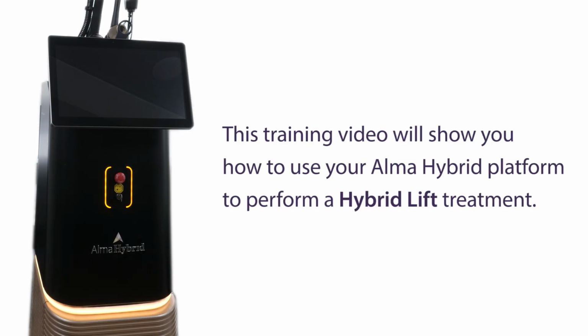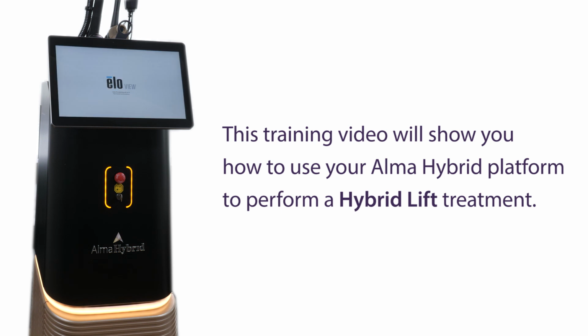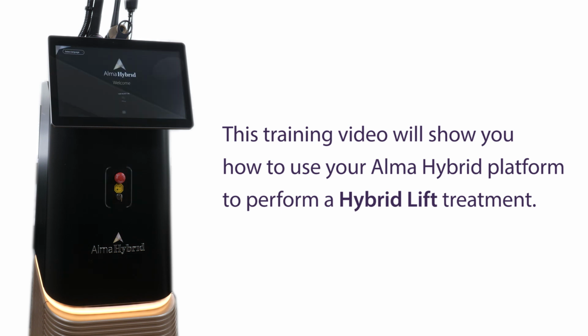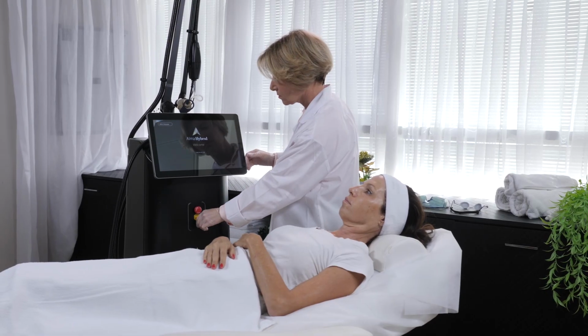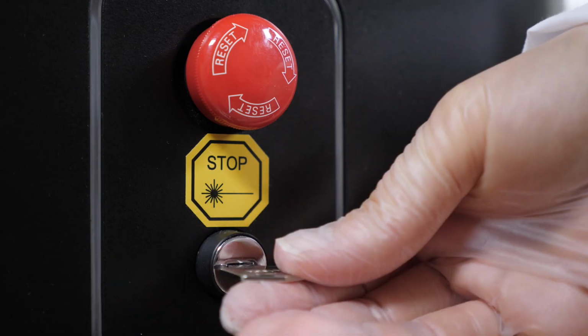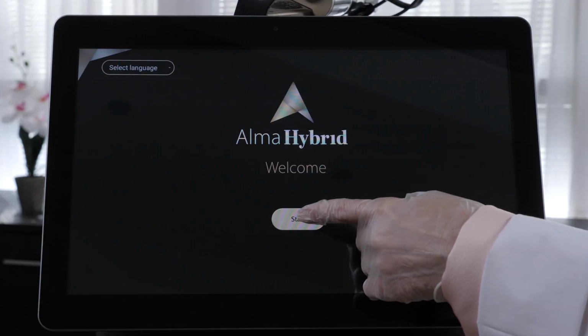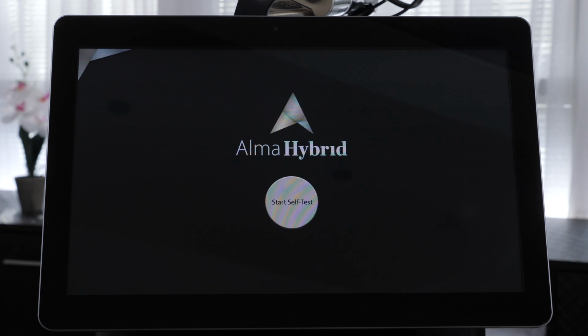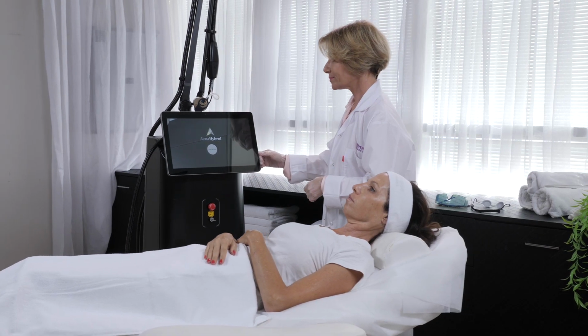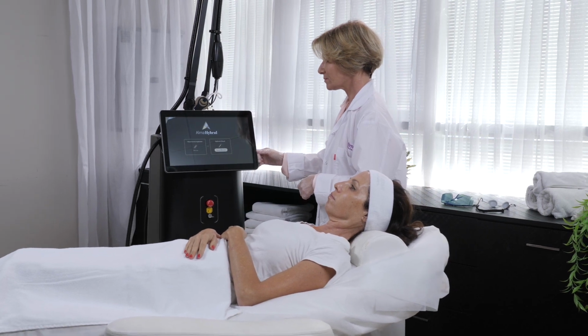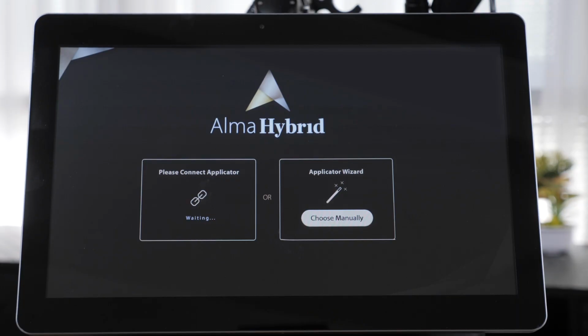This training video will show you how to use your Alma hybrid platform to perform a hybrid lift treatment. Turn the key clockwise. Tap the Start button. Press Start Self-Test. The platform performs a quick self-test. Upon completion of the self-test, the main menu will appear. You can either choose to browse through the wizard or connect an applicator.